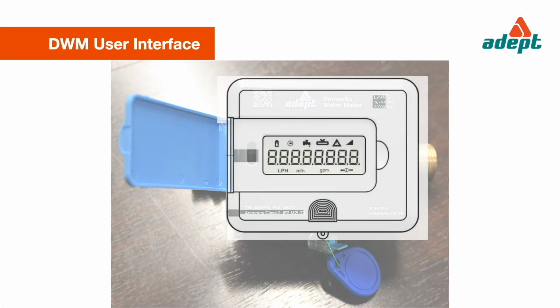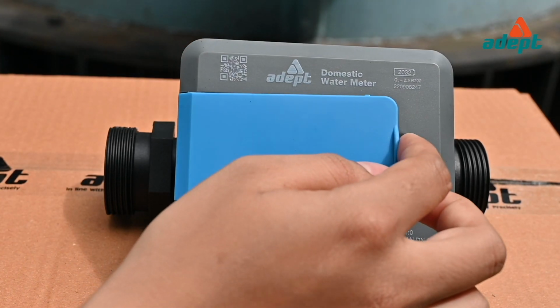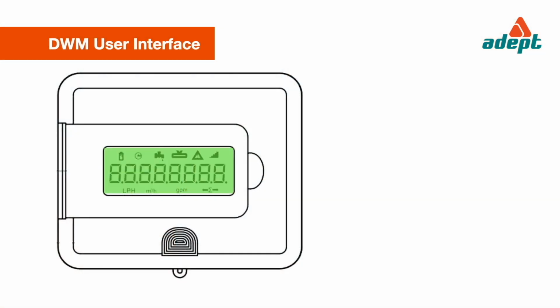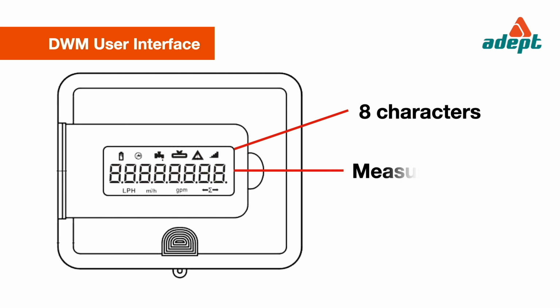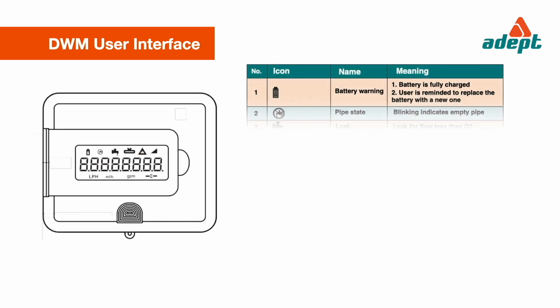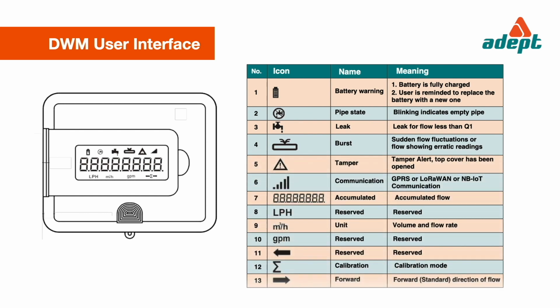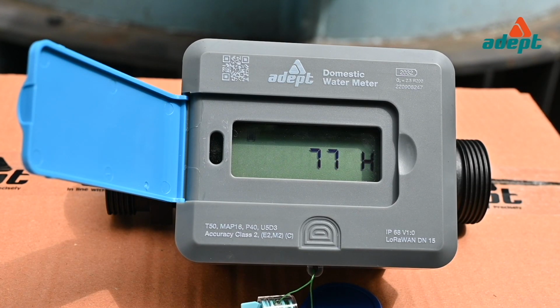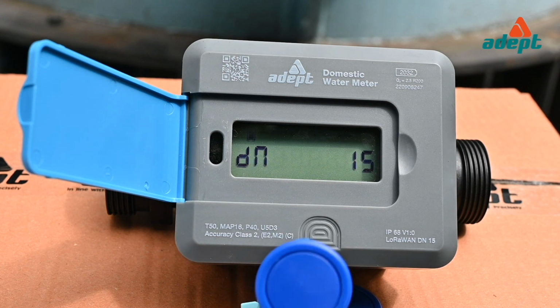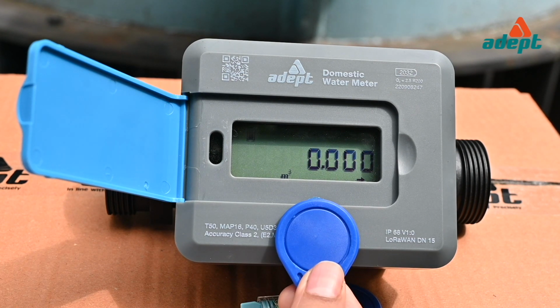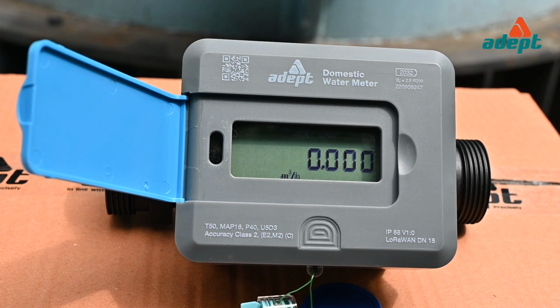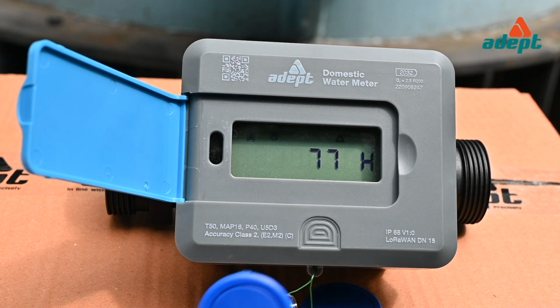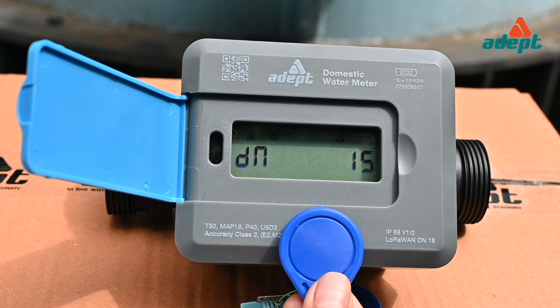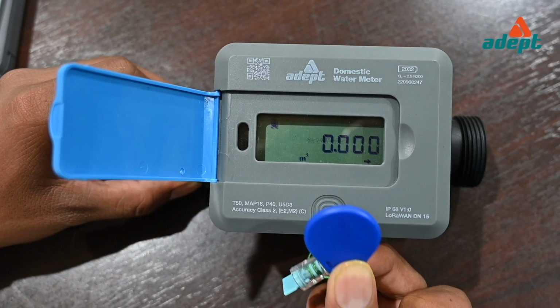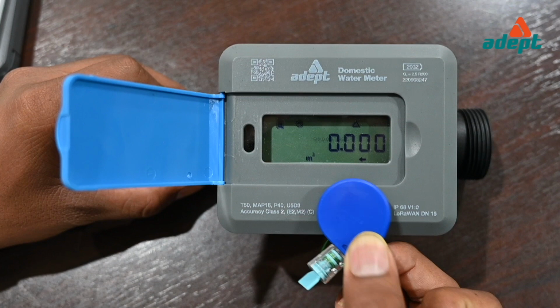DWM User Interface. The interface includes an easily readable LCD screen consisting of 8 characters, measuring units, and information icons. Menu operation. The display is normally in the run mode and indicates the totalized flow value. You can navigate the menu by using a flat disk magnet which activates an internal magnetically sensitive switch. Note: the use of a short touch of less than 5 seconds and a long touch of more than 5 seconds is required to navigate through the menu.